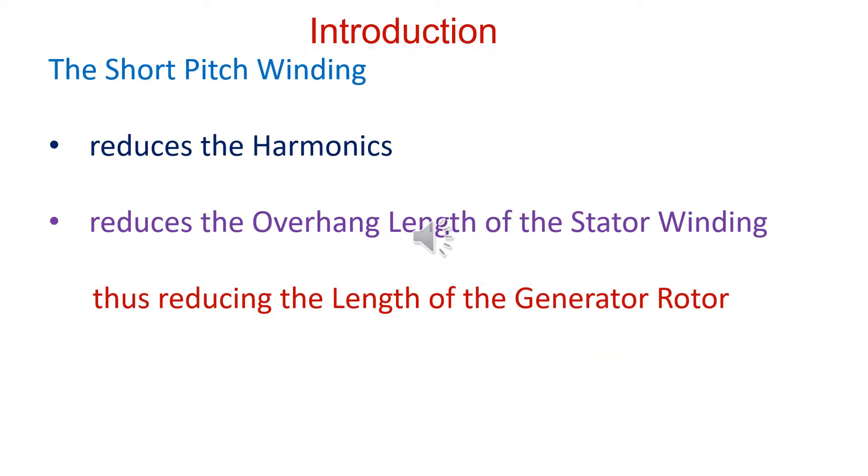Though KVA rating of the electrical generator is slightly reduced due to short pitch winding, the advantages are many. Short pitch winding reduces harmonics. It also reduces overhang length of the stator winding, thus reducing length of the generator.